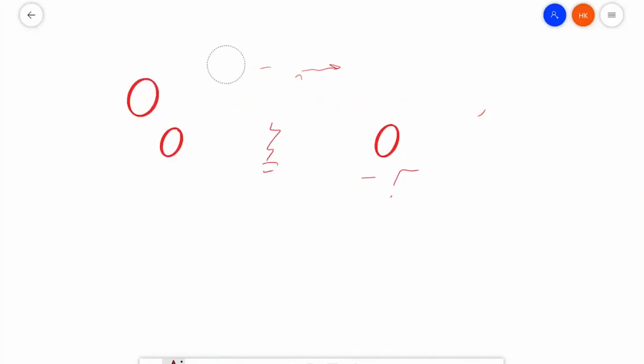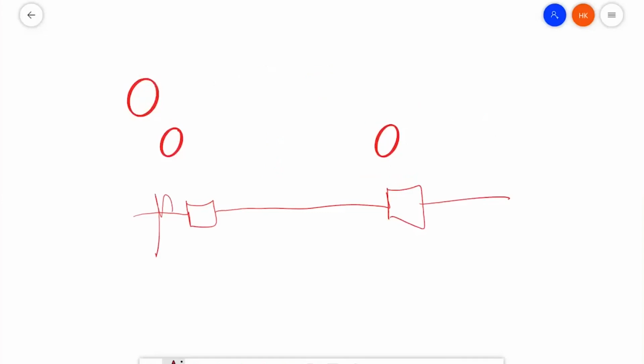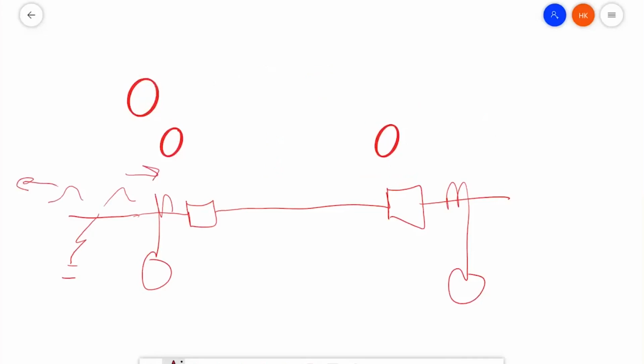Somehow I can't erase these circles. I don't know why. I'll just draw down here. So imagine now we have an external fault, and we have the fault somewhere out here. Again, we're going to have traveling waves launched from the fault point in both directions. But only this one is the one that our relays are going to see. So relay number 1 here is going to see this traveling wave in the same polarity as the primary traveling wave because it's entering on the polarity of the CT. So this relay is going to see the traveling wave in the positive direction.